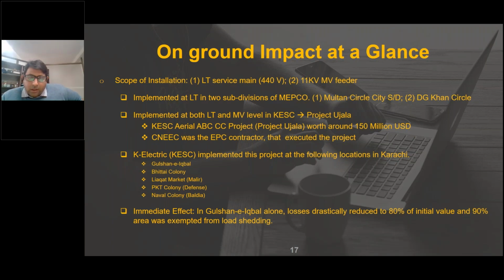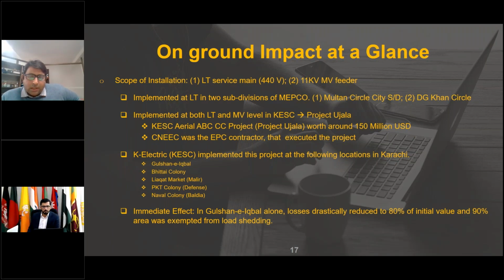The immediate effect of these covered conductors is that in Gulshan Iqbal alone, losses drastically reduced to 80% of its initial value, and 90% of the area was exempted from load shedding. This is because, per a directive from the Supreme Court, if the revenue from any feeder is less than 50% due to pilferage or other losses, it can be cut off from the system to recover the rest of the system.